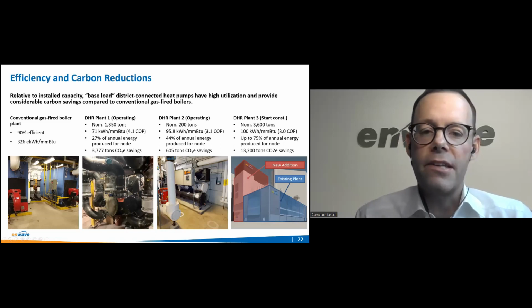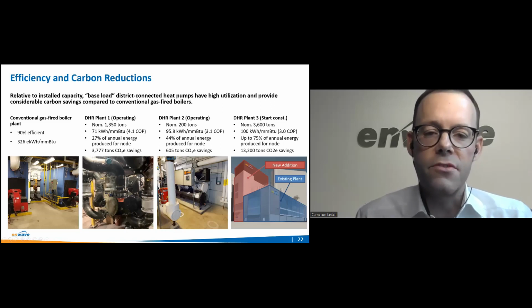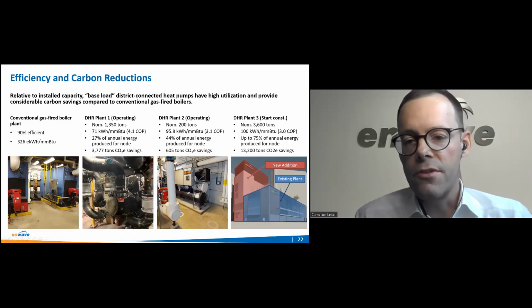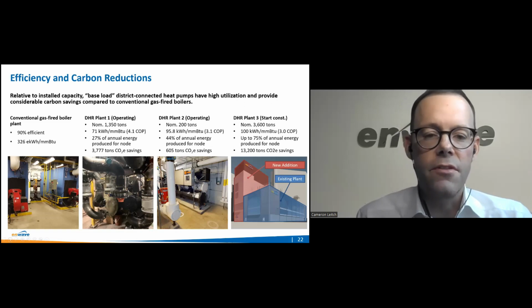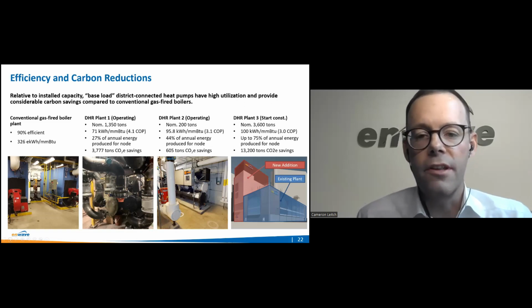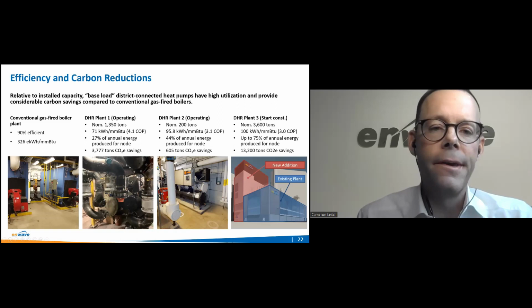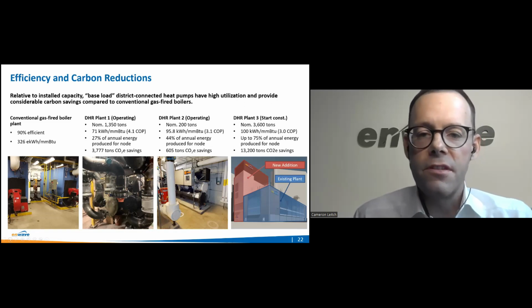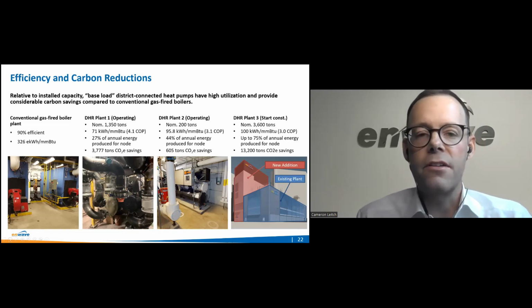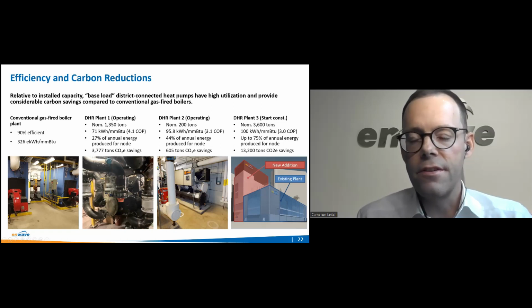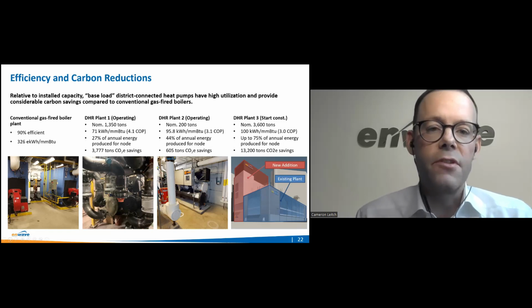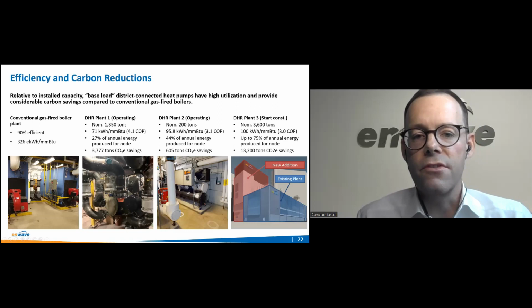And DHR Plant 3 hasn't been constructed yet, but will feature 2 1,800-ton compound centrifugal chillers capable of producing 170 F coincident with 39 F chilled water. It will be online for the winter of 2024. As we can see, the efficiency of the individual plants varies depending on compressor technology and lift conditions.